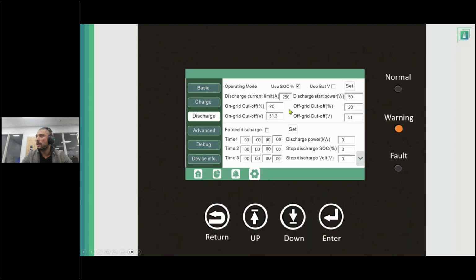And then the on-grid cutoff, I'm going to lower it to however I want my battery to discharge. For warranty purposes, we allow an 80% depth of discharge. So if I want to, in self-consumption mode, discharge from 100% to 20%, I would just put 20% here.